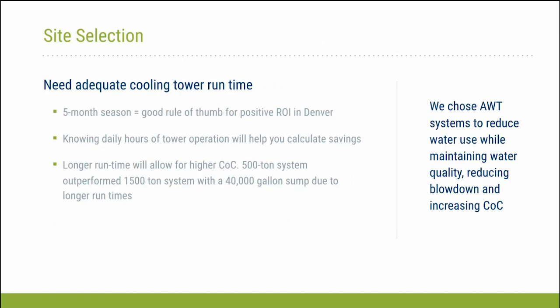As Jesse alluded to, we've done a number of cooling tower water treatment installations here, both at the Denver Federal Center and other sites across our region. At least here in Denver and most of our sites, we have a pretty standard five-month cooling season, and that's generally the minimum standard we look for to see a positive ROI with one of these technologies. Knowing your daily hours of tower operation gives you a better idea of how much potential you have, since the more we see these towers running, the more potential savings are available.